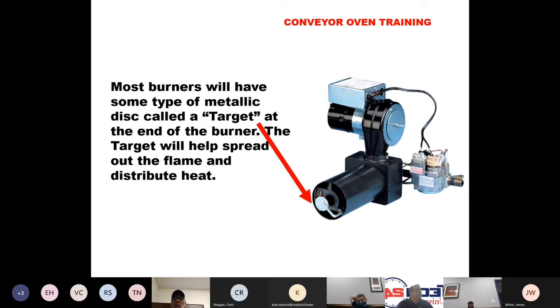Most of these burners are going to have some type of metallic disc that's called a target at the end of the burner. That target is there to help spread out the flame and help distribute the heat. It also has some effect on flame current by keeping some of the flame back towards the burner. So if you have a missing target, that can cause low flame current issues as well.